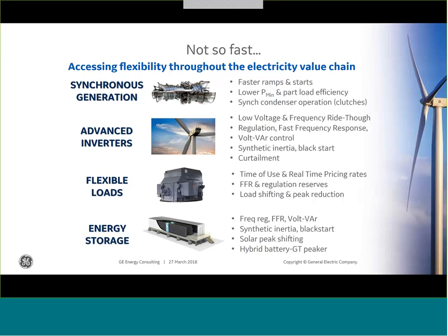In terms of the renewables themselves, wind and solar, the inverters are getting much more sophisticated so that a lot of the ancillary services, the grid services that storage can provide, can also be provided by the renewables themselves. So regulation, fast frequency response directly from wind and solar is certainly a technical capability. In fact, the speed of response for a lot of those resources is even faster than conventional thermal generators.